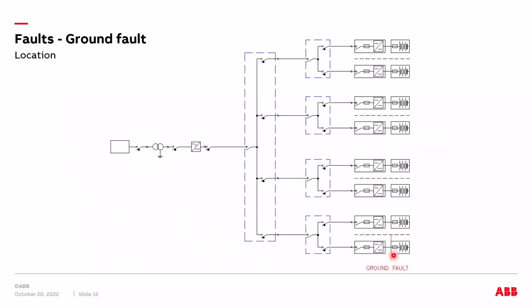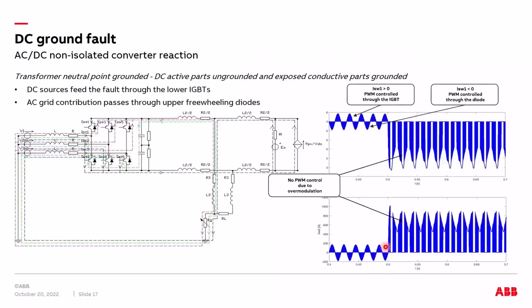If we have a ground fault, basically the probability to have a ground fault is higher at this point. This means directly on board of the vehicle and between, let's say, the internal architecture of our DC charger and the exposed conductive part, if the chassis of the DC charger is not made of an insulating material. So if we have a ground fault, here we have to consider the ground connection of a medium voltage/low voltage transformer. Here we consider a non-isolated converter, because if we have an isolated converter, both the AC-DC converter and the DC-DC converter, we don't have a ground fault.